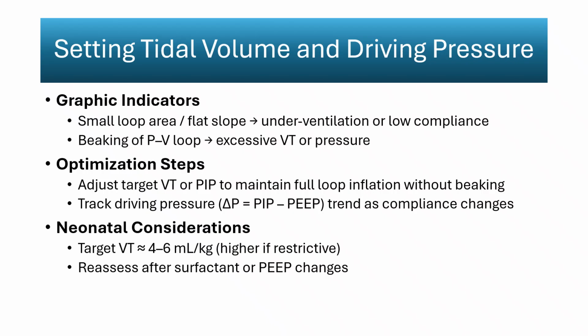In neonates, typical tidal volume targets fall around 4 to 6 milliliters per kilogram, with slightly higher values needed in restrictive processes. These targets are dynamic rather than fixed. Surfactant administration, shifts in lung water, or changes in PEEP alter the compliance curve, and tidal volume must be reassessed after each of these interventions to avoid either underventilation or unrecognized stretch injury. Using graphics to detect these shifts allows the ventilator to be aligned with the infant's lung mechanics in real time.